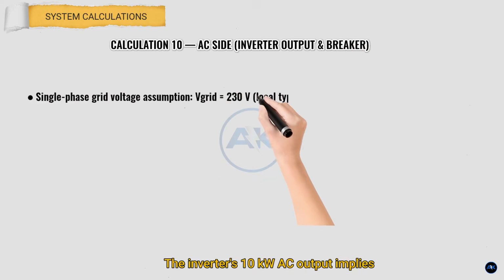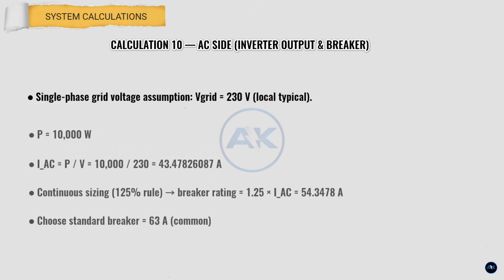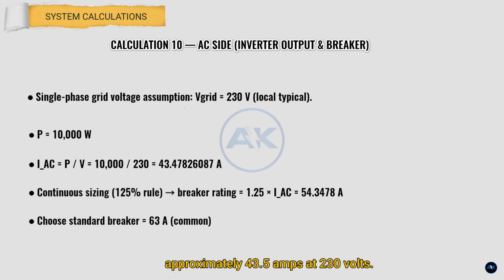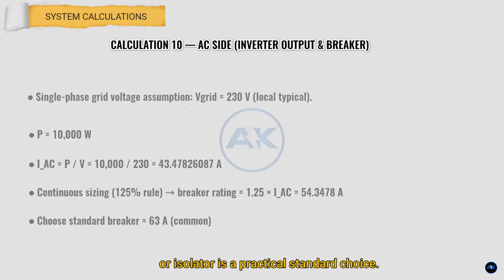Calculation 10. AC side, inverter output, and breaker. The inverter's 10 kilowatt AC output implies approximately 43.5 amps at 230 volts. Using a 125% continuous load rule gives a breaker near 54.3 amps, so a 63 amp AC breaker or isolator is a practical standard choice.